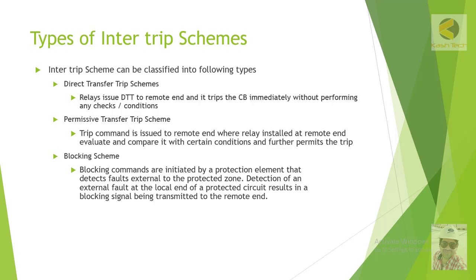The third type is the Blocking scheme. In this scheme, the blocking commands are initiated by a protection element that detects a fault external to the protected zone. The detection of an external fault at the local end of a protected circuit results in a blocking signal being transmitted to the remote ends.